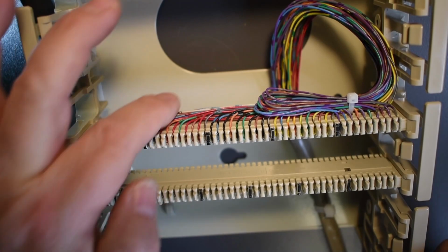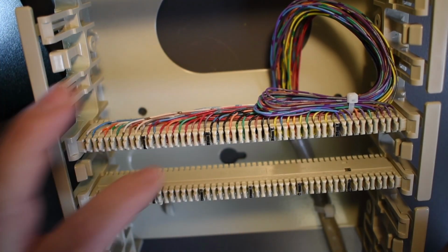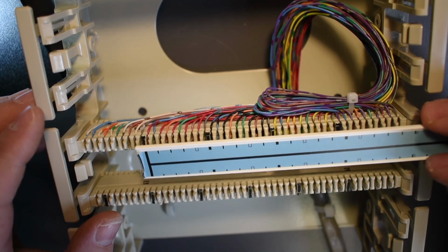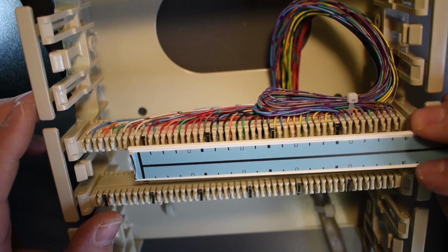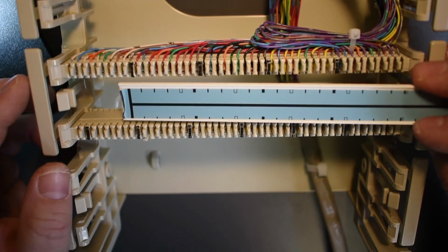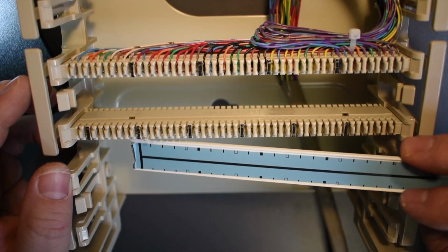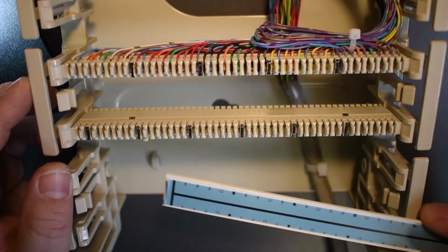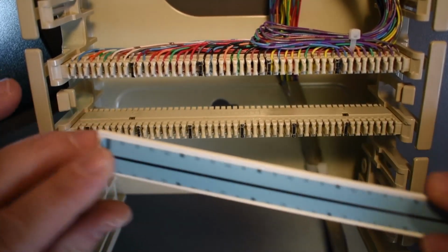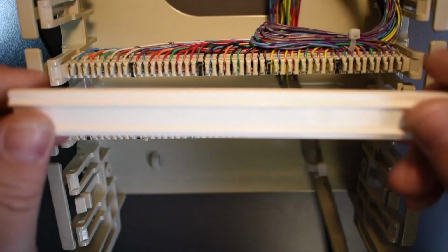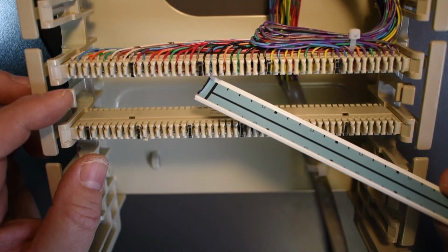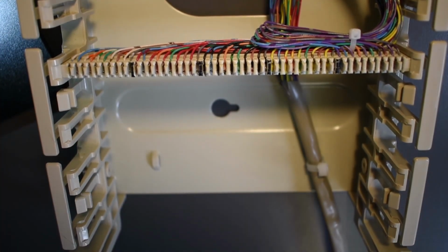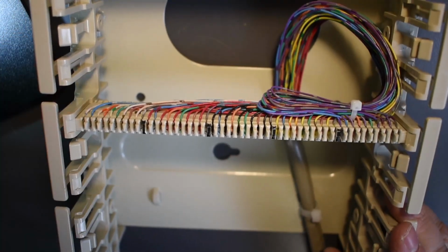So those are going to have to be hidden within that pair and covered by the designation strip after they are done. Now obviously, if we were punching this one here, we would not be punching that from the top, running the wires from the top. We would be running the wires from the bottom here. So once we flip it upside down, those wires are going to end up on the inside of the pair of those strips. Okay? So here's the flippage.